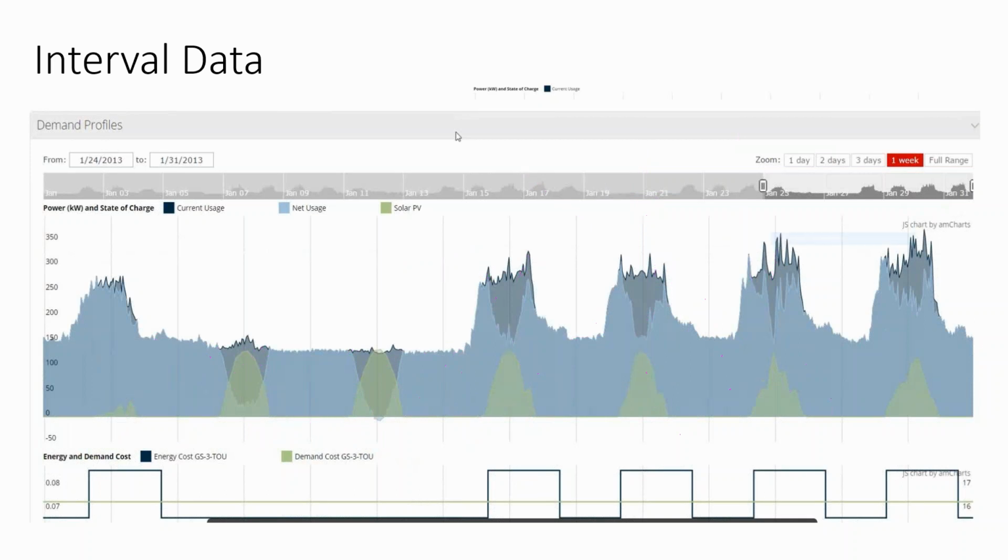And so we can have the more cost-effective flooded lead acid taking care of our base, and the more responsive, efficient lithium ion taking care of the spikes. And those concepts are a little bit ahead of what the manufacturers are willing to support at this time.